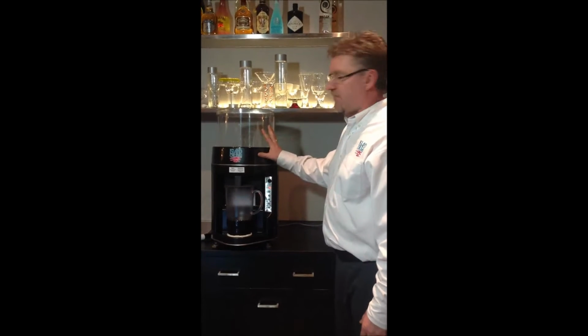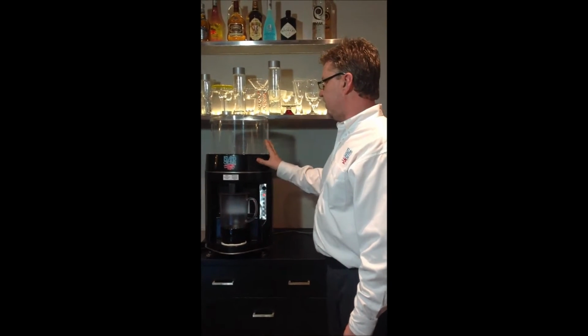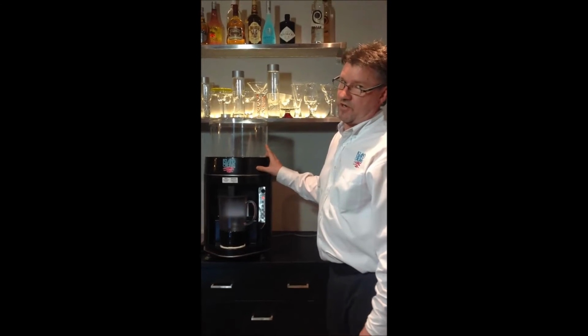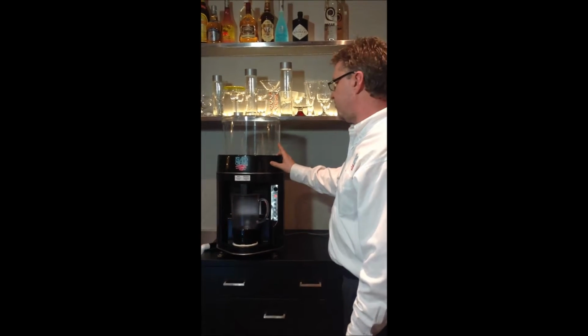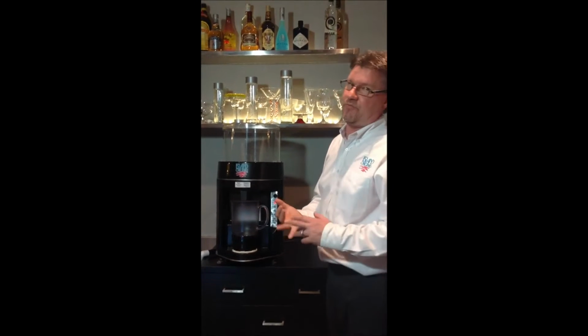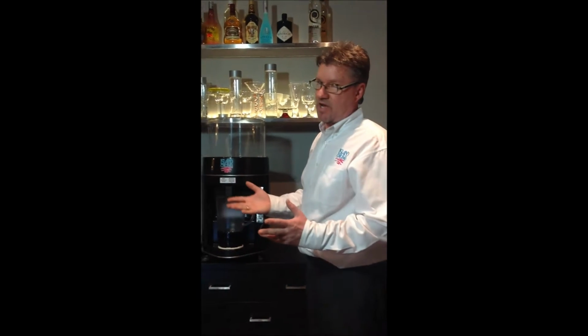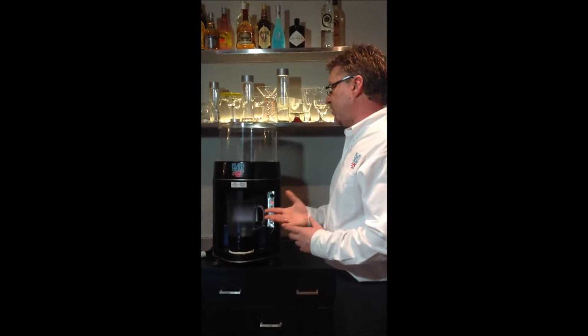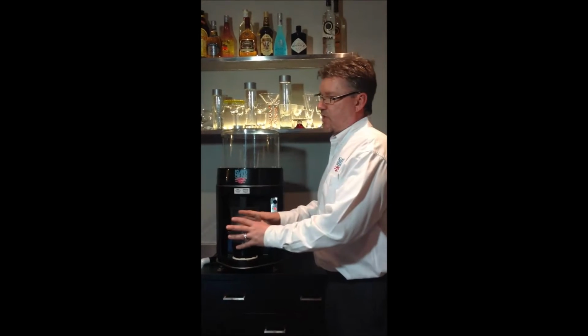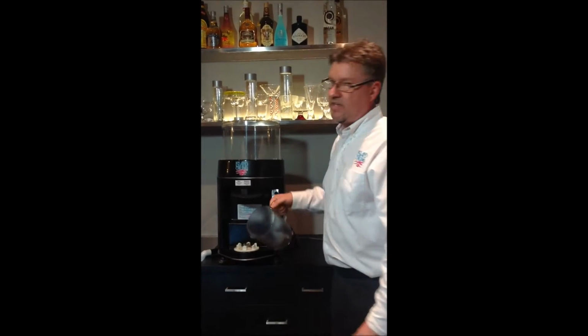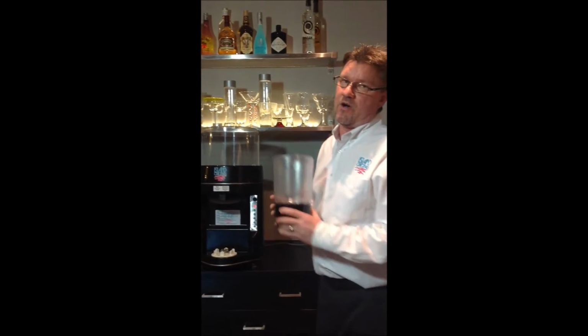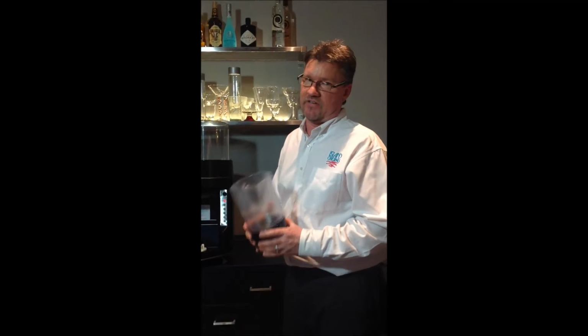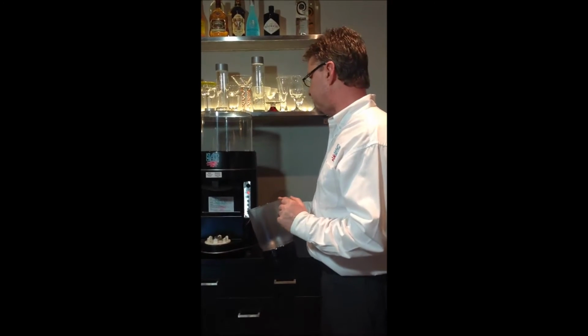Now, I've mentioned shaved ice will flip the breaker. Another reason the breaker can get flipped is from what we call a foreign object. Foreign objects can be a couple things — it can be change, it can be caps from a beer bottle, for instance. Generally that happens if you go to an ice well behind the bar to get ice for the machine. Never scoop the ice out of the ice well — always go right back to the source, to your actual ice maker. If you go to the ice well, 9 times out of 10, that's where you're going to find a foreign object. So always make sure you go directly to the source, to your ice maker, for ice.